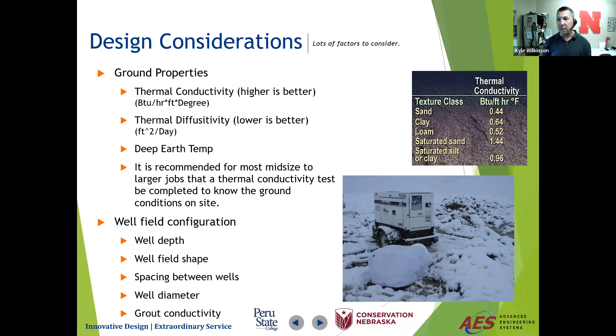And Kyle mentioned the 20-foot typical spacing. So if it was heating dominated and you're in Wisconsin, we did a project out there, the wells get closer together, like 15 feet apart. You go down to Texas and it's the other way around. You may be 30 feet apart. So it just makes a difference whether it's a cooling dominated or heating dominated climate.